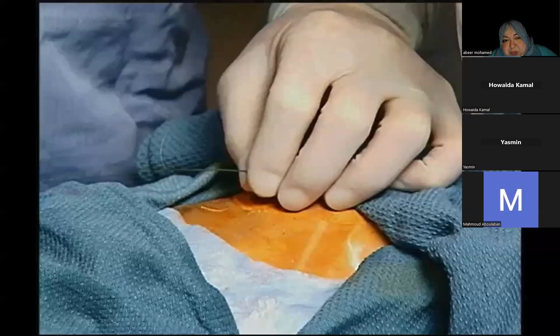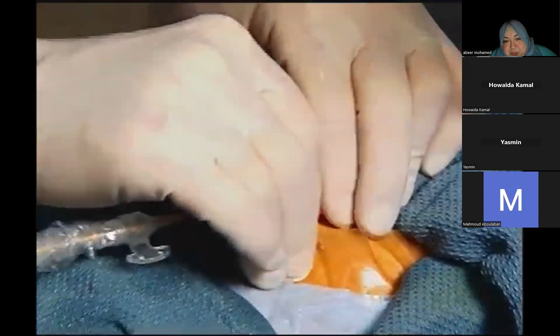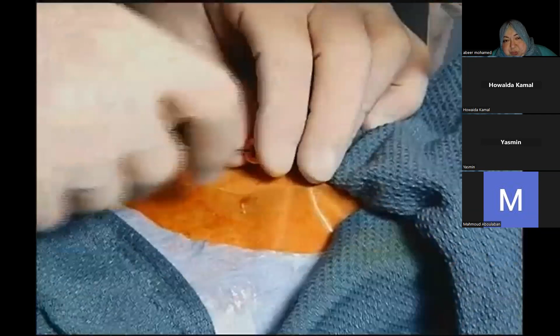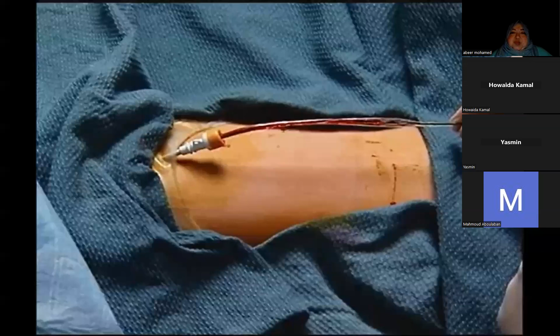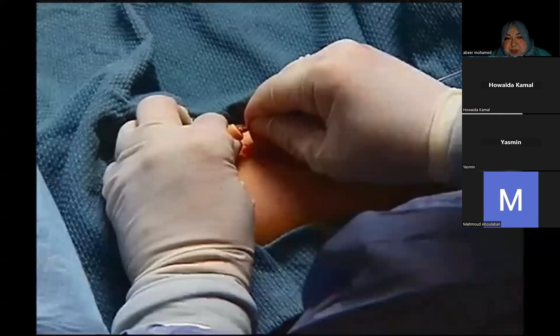Advance the balloon catheter over the guide wire until the guide wire exits the female luer fitting at the Y fitting of the catheter. While controlling the guide wire, advance the catheter into the sheath. Hold the balloon catheter close to the hub of the sheath to avoid kinking the catheter or inner lumen. While the pre-folded balloon membrane is easily inserted through the sheath, its smooth longitudinal folds can sometimes act as a conduit for arterial blood under pressure.